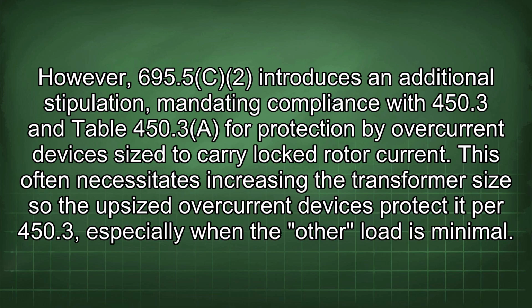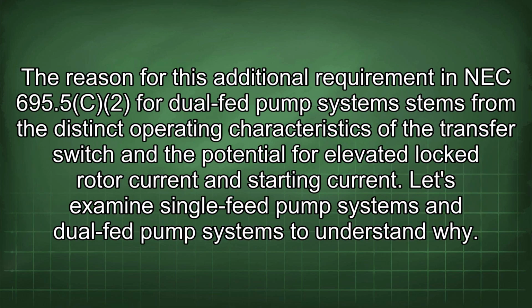sized to carry locked rotor current. This often necessitates increasing the transformer size so the upsized overcurrent devices protect it per 450.3, especially when the other load is minimal. The reason for this additional requirement in NEC 695.5 C2 for dual-fed pump systems stems from the distinct operating characteristics of the transfer switch and the potential for elevated locked rotor current and starting current. Let's examine single-feed pump systems and dual-fed pump systems to understand why.